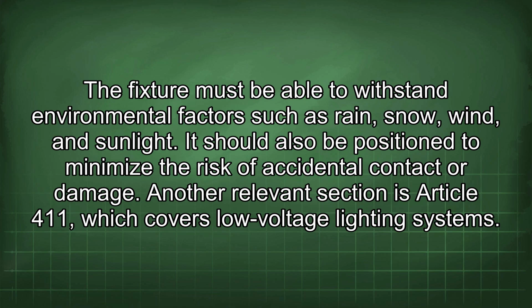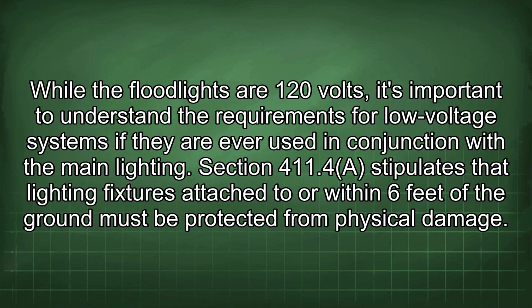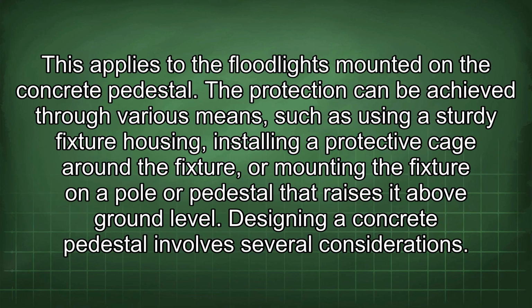Another relevant section is Article 411, which covers low-voltage lighting systems. While the floodlights are 120 volts, it's important to understand the requirements for low-voltage systems if they are ever used in conjunction with the main lighting. Section 411.4 stipulates that lighting fixtures attached to or within 6 feet of the ground must be protected from physical damage. This applies to the floodlights mounted on the concrete pedestal.